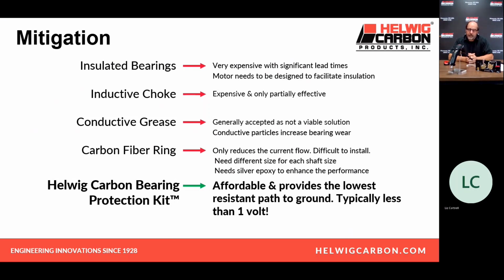Conductive grease, we will never recommend conductive grease. We've done extensive testing on it. It actually encourages bearing discharges. If someone is asking you to use conductive grease in your bearings, please be cautious. Do your homework. Give Helwig a call. We'll be glad to show you our tests that would very much discourage you from using conductive grease in your bearings. It sounds like a good idea.